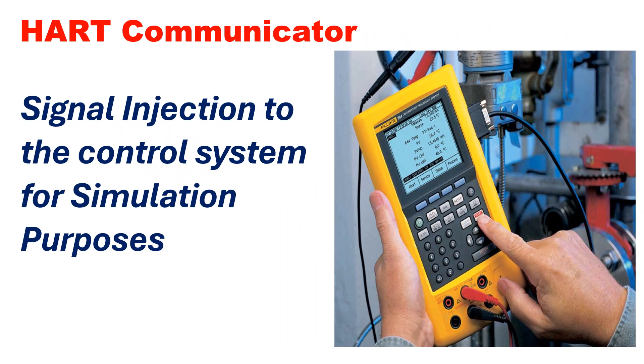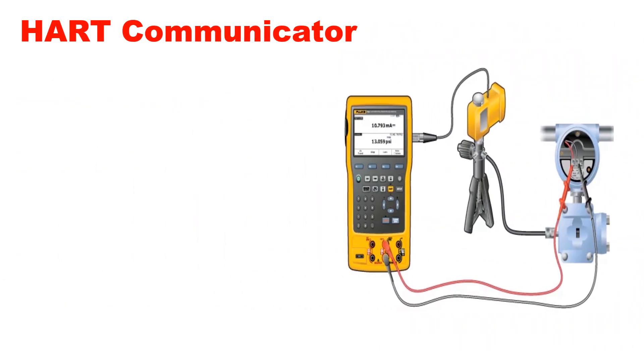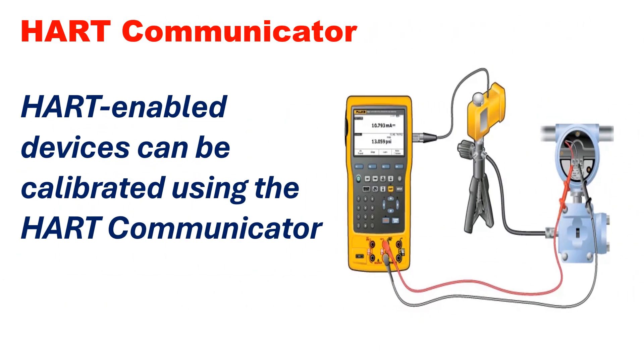You can also perform signal injection to the control system for simulation purposes using HART Communicator. Additionally, HART-enabled devices can be calibrated using HART Communicator, enabling technicians to perform calibration tasks easily, with adjustments to sensor values and other parameters also made very easily.